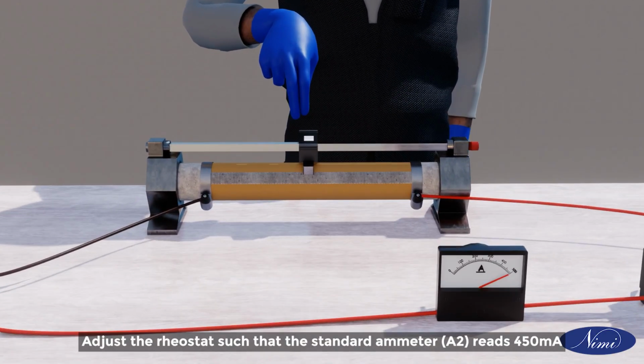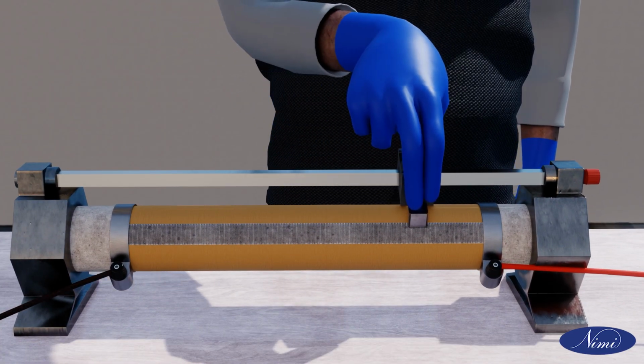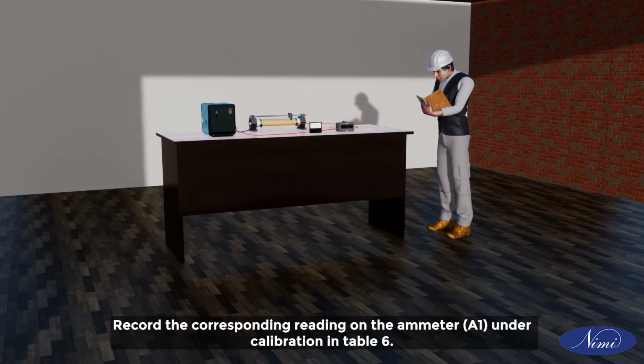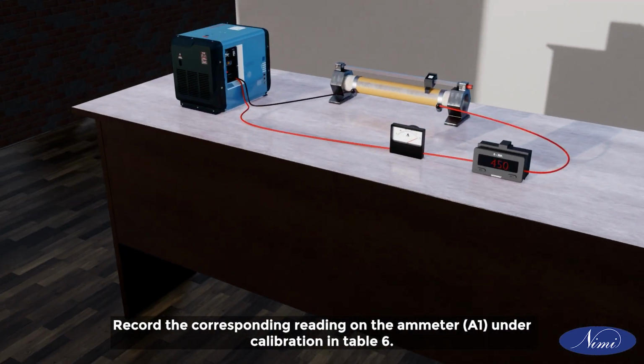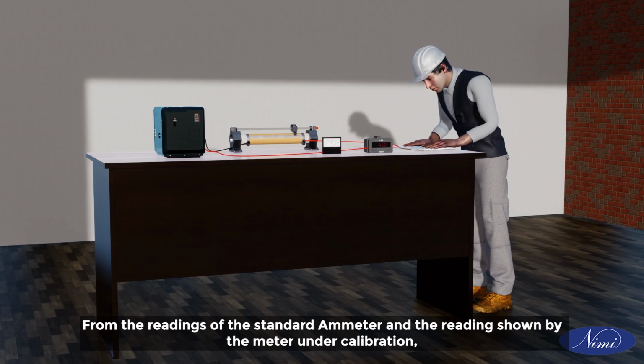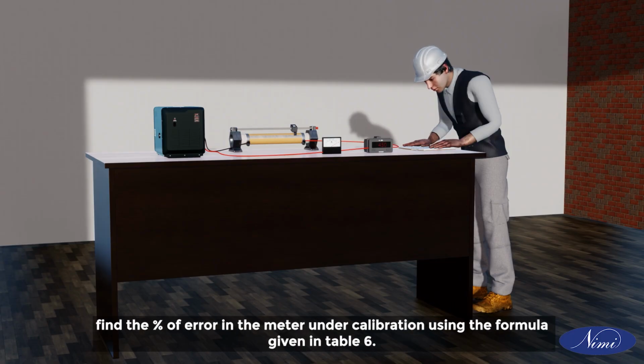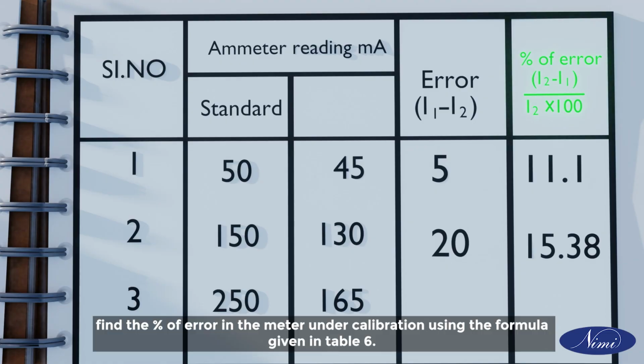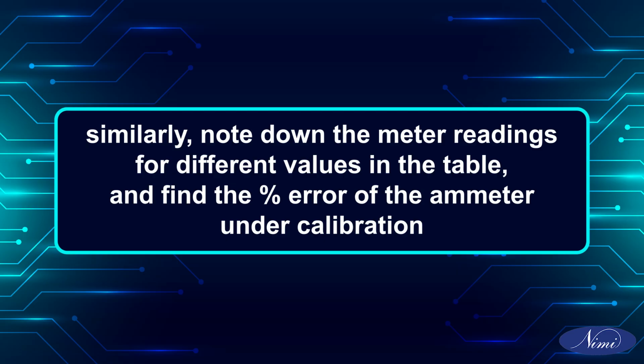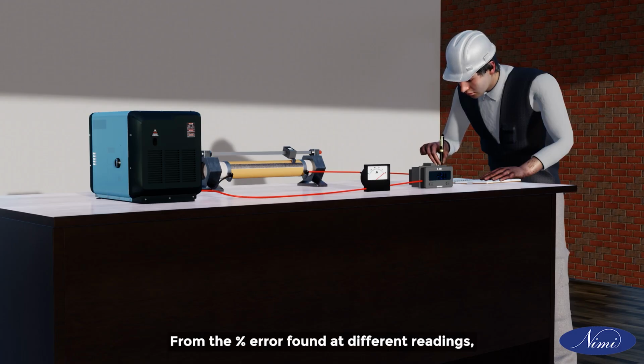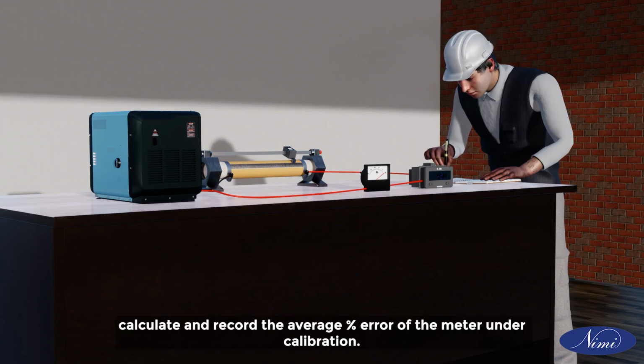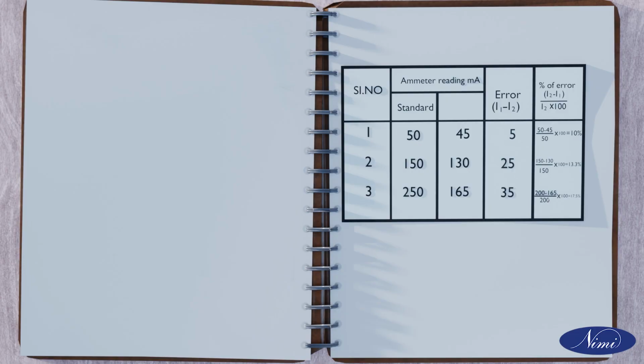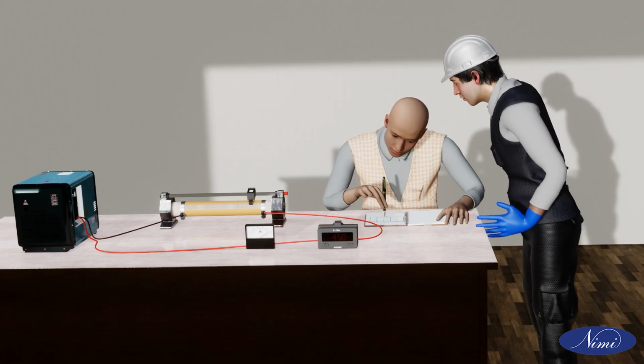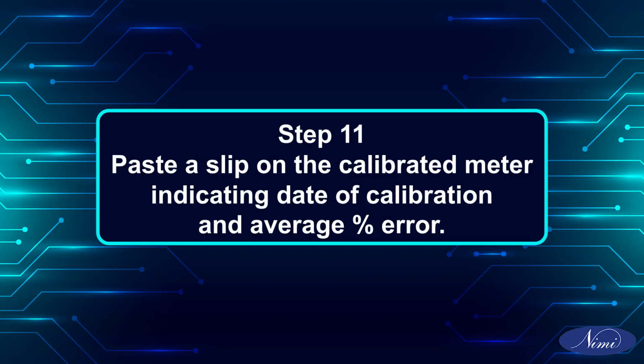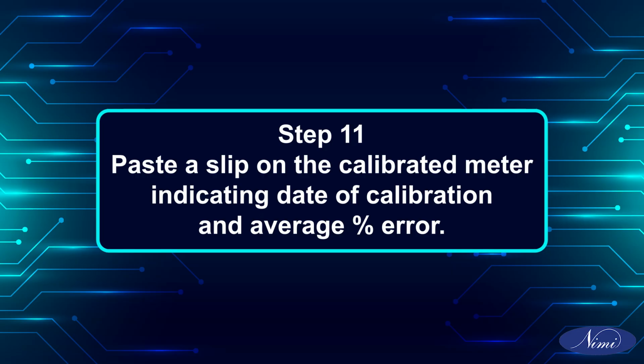Adjust the rheostat such that the standard ammeter A2 reads 450 mA. Record the corresponding reading on the ammeter A1 under calibration in Table 6. From the readings of the standard ammeter and the reading shown by the meter under calibration, find the percentage of error in the meter under calibration using the formula given in Table 6. Similarly, note down the meter readings for different values in the table and find the percentage error of the ammeter under calibration. From the percentage error found at different readings, calculate and record the average percentage error of the meter under calibration. Get your work checked by the instructor. Paste a slip on the calibrated meter indicating date of calibration and average percentage error.